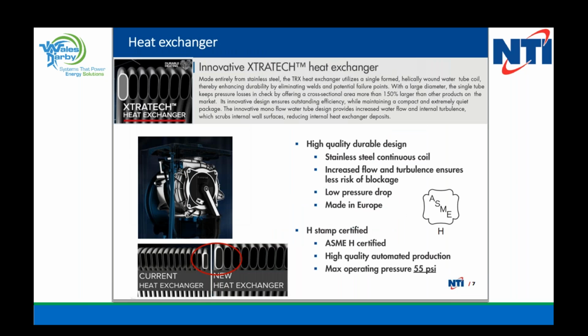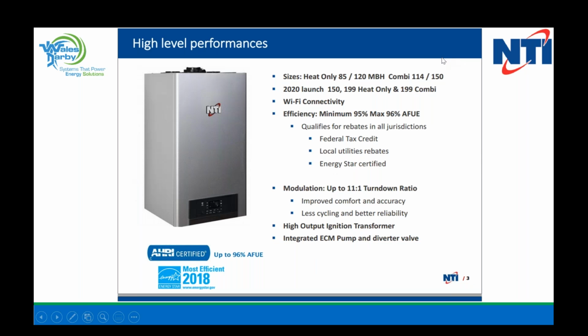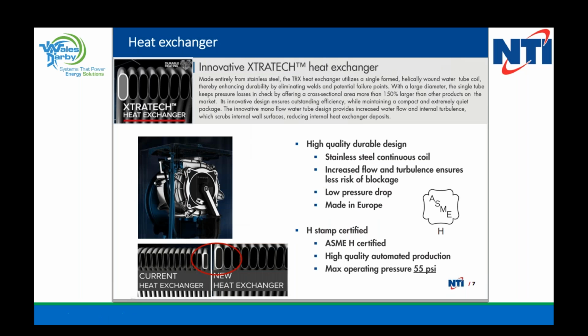Thank you. So here's a picture of this heat exchanger, which is different than the standard water tube heat exchangers that everybody is familiar with. First off, this is one continuous coil. So it's not a two-piece coil, it's one continuous coil. It also has the largest passageways you can see on the bottom. That means we can increase our flow rate, create a lot of turbulence to make sure that there should be no buildup of any type of deposits inside the actual coil. Gives us the ability to have a much lower pressure drop. All right, so we're the guys on the street that have this.